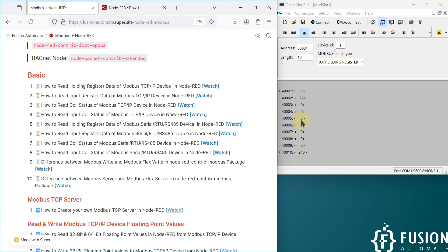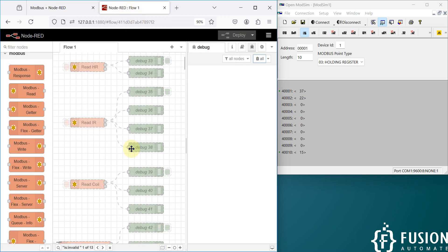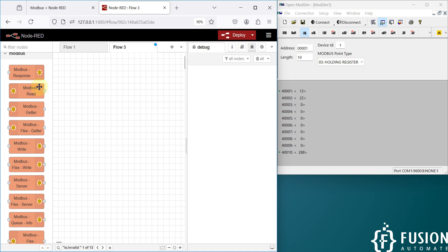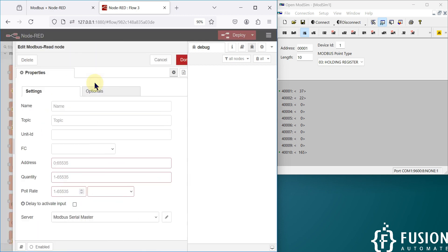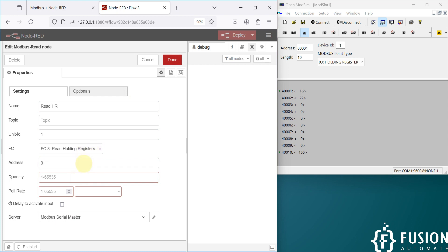Now I want to read this data — so how can we do that? We go to Node-RED. This is the flow from our previous sections where we were reading data from a Modbus TCP device. I'm going to create one more flow using the Modbus Read node. Here we are reading the holding register — HR stands for holding register. The unit ID is 1, function code is 3 because we are reading holding register values, starting address is 0, quantity is 10, and the poll rate is 2 seconds.